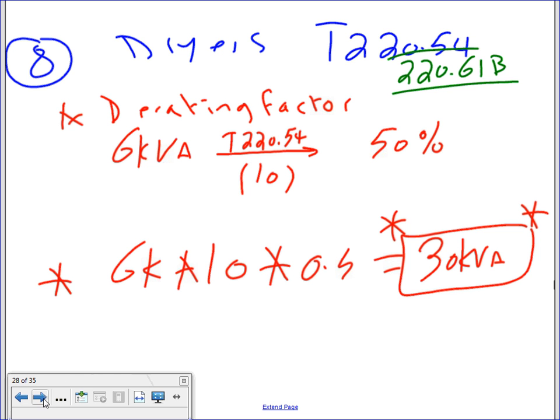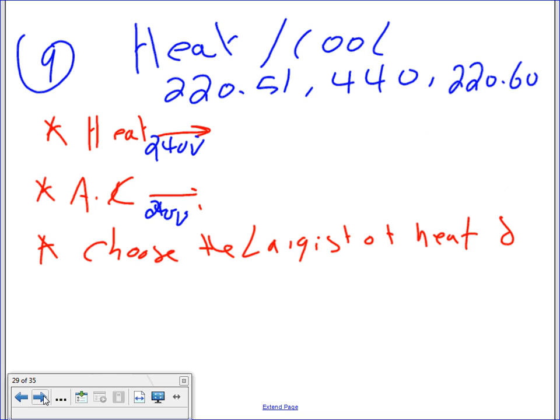Let's go to the next type of load that we have. The next type of load is heat-cool. For the heat-cool, guys, they are non-simultaneous loads, 220.60, 220.51, and 440. 220.60 tells you to do the math for both of them and pick the largest of the heat or the cool. For heat at 240, I have 8 kW heaters, 10 of them. That will give you 80 kW.